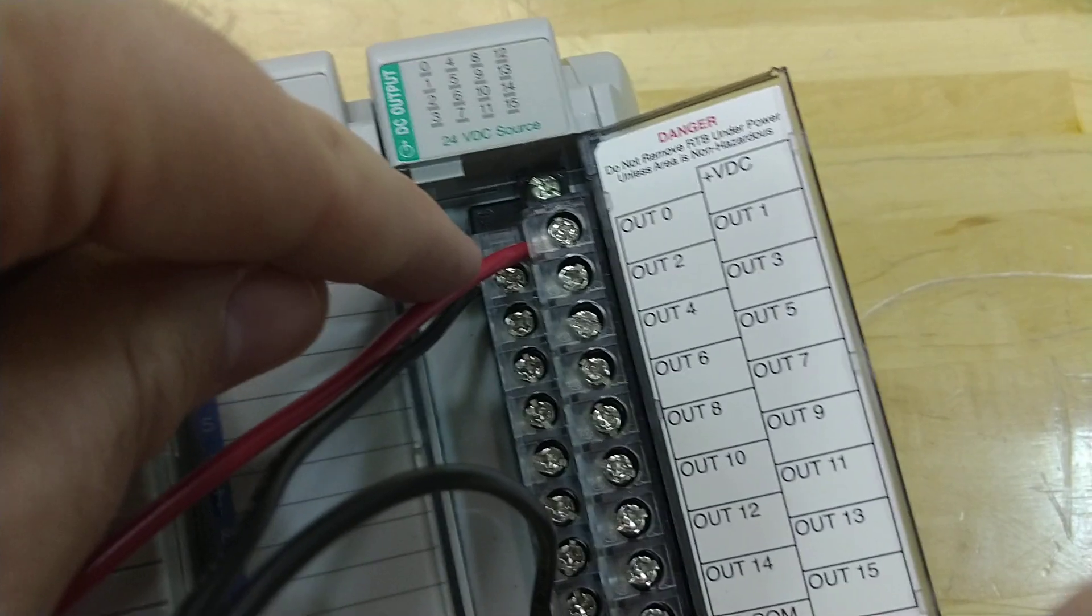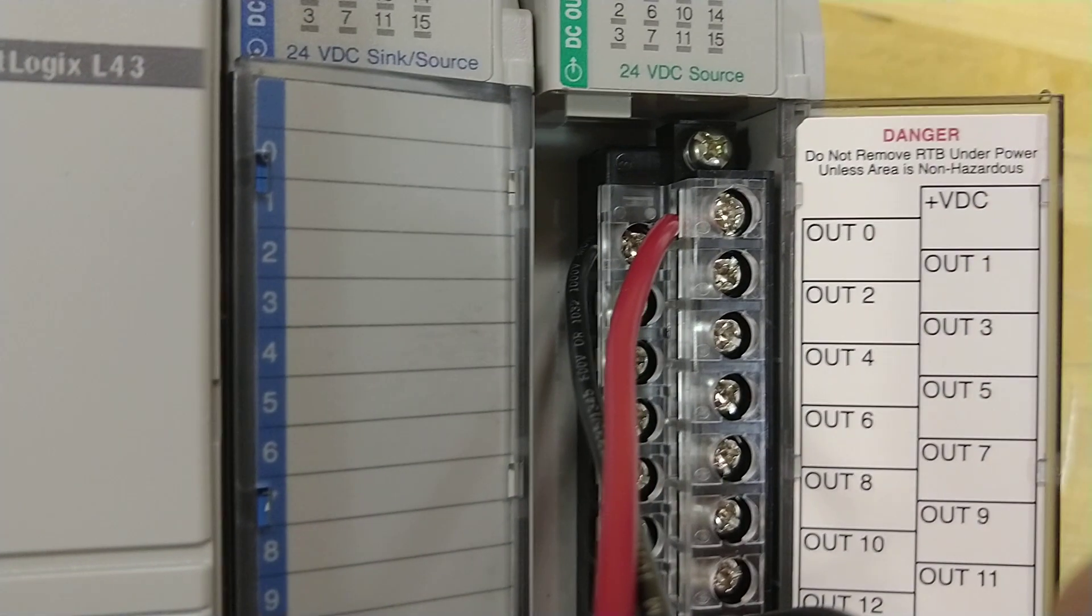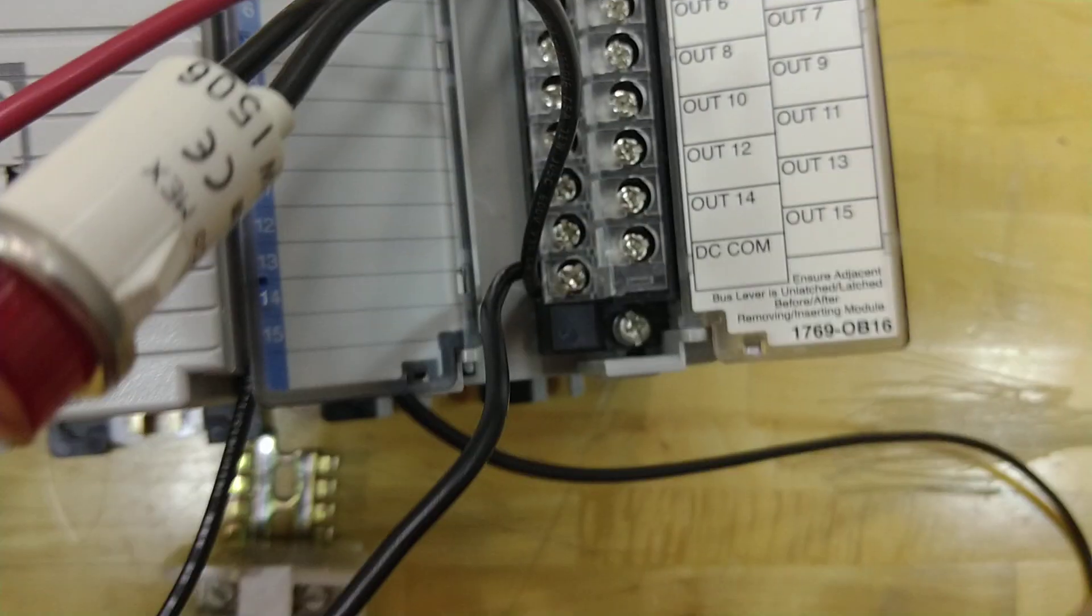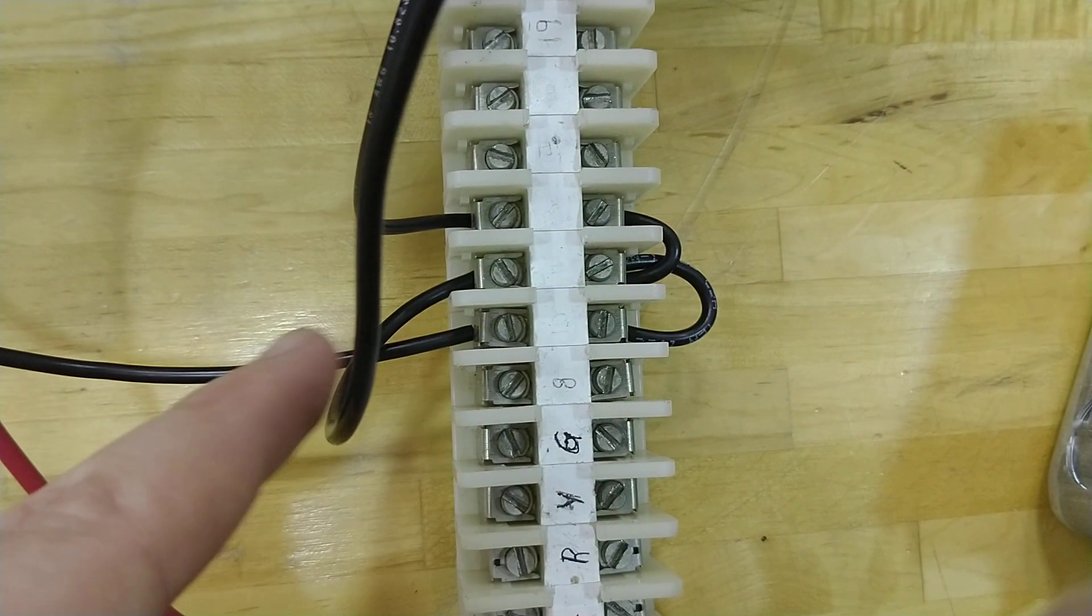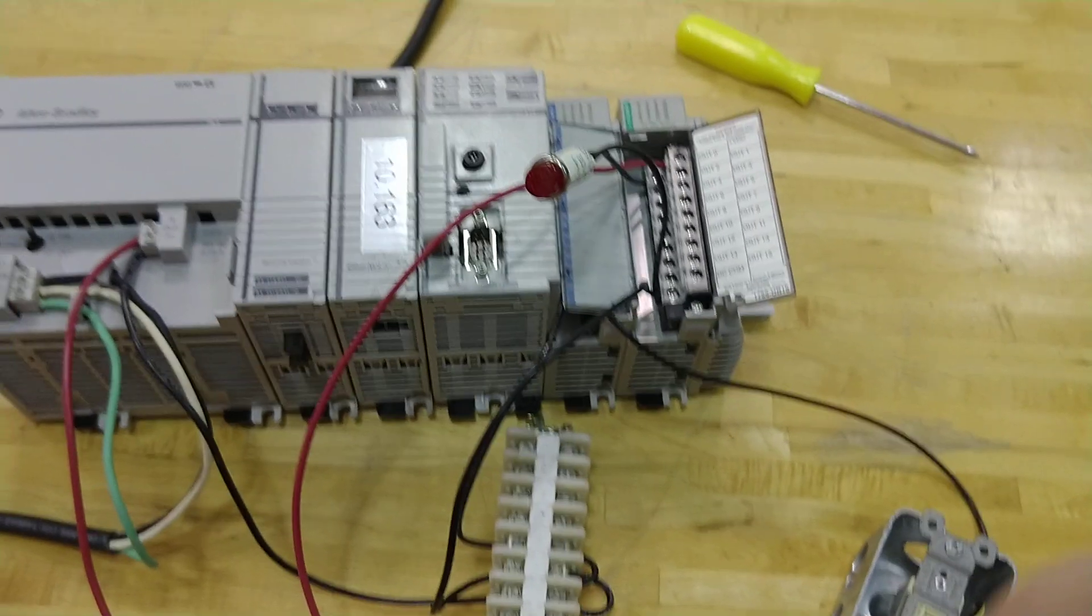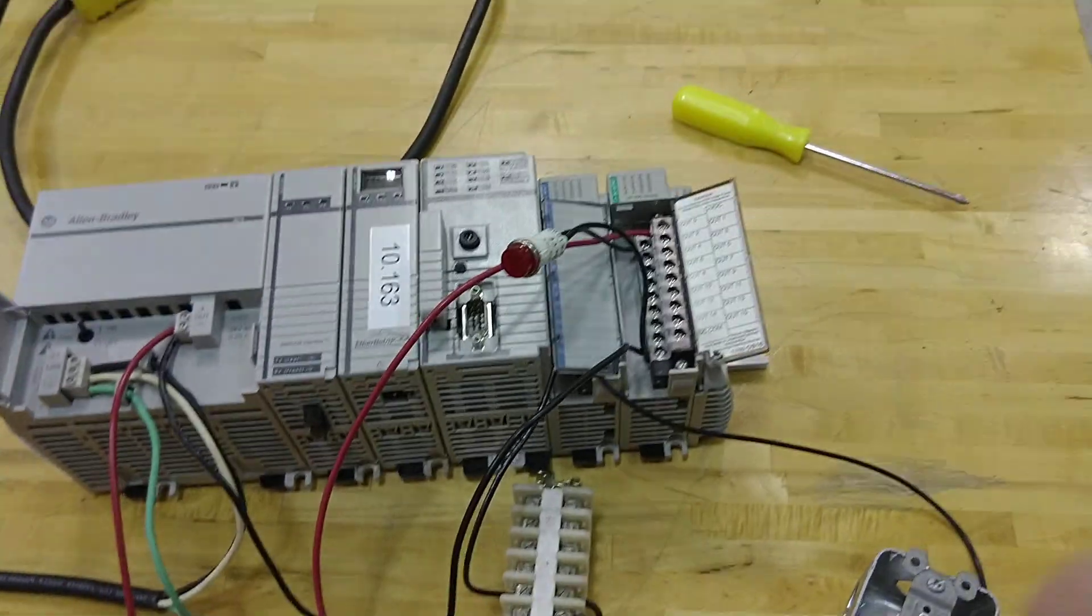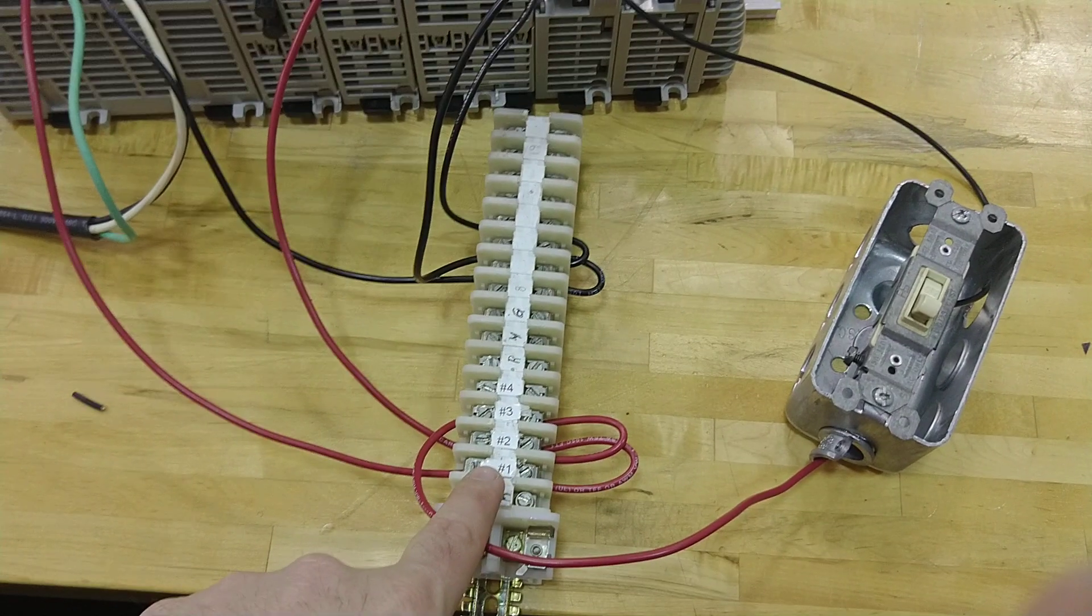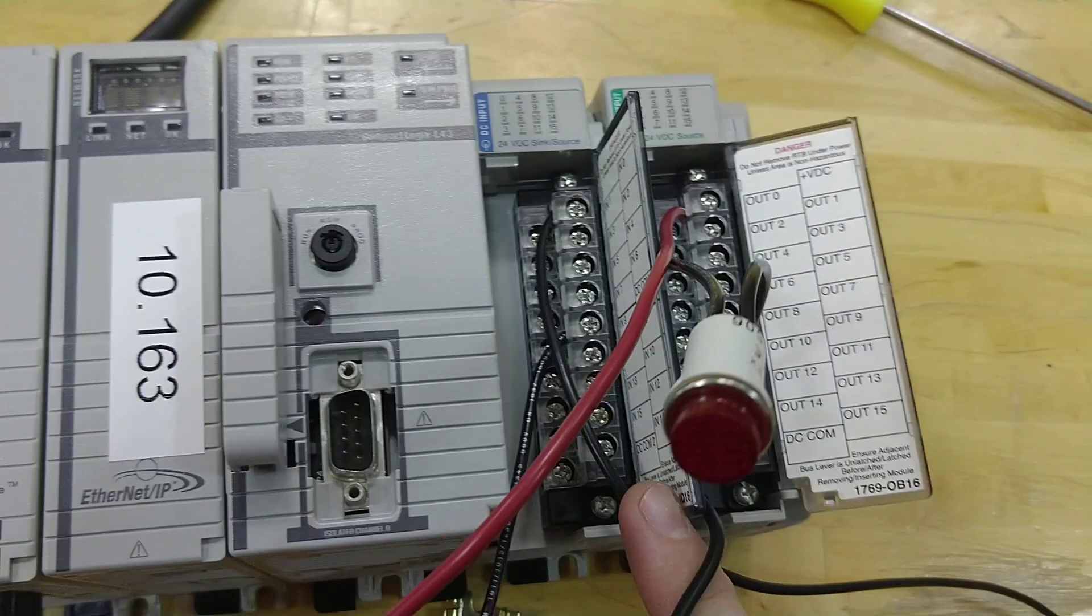With the output, I have that cable, that cord going up here. When this turns on, it sends a signal, and you can kind of see that out there. Out the out zero, through my light, and it goes right to the DC common. The common then is tied through jumpers to the common coming out of here. This is a little more complex, but it's the same basic principle. The only difference between this and the other one I showed you is that you have to run your power to your cards. This is more consistent with what you will see in industry.